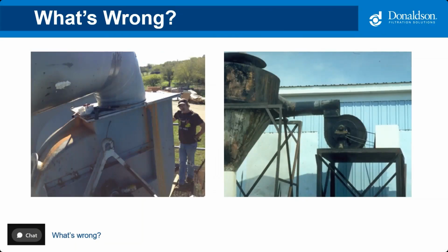I think these are my favorites. What do we see happening here? Okay, we have elbow issue, outlet design, restricted outlet. Most people pointing to the outlets. Oh, I saw a lack of belt guard. Hey, that's a great observation. I've been looking at this, I don't know how many seminars, and I never even considered that.